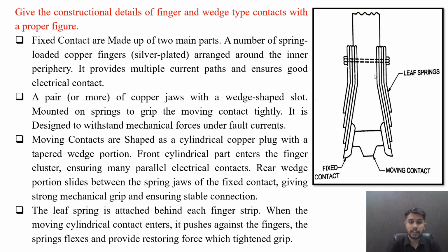The leaf spring is attached behind each finger strip. When the moving cylindrical contact enters, it pushes against the finger. The spring flexes and provides a restoring force which tightens the grip. So this is how the construction of finger and wedge type contacts is carried out.